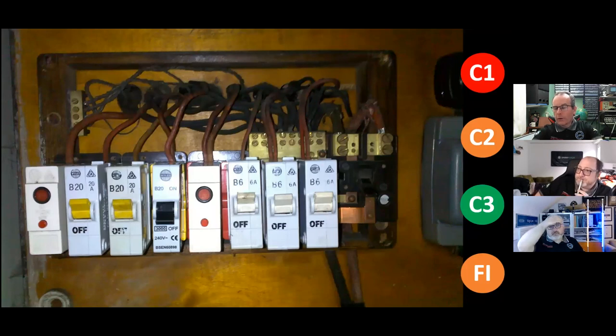And quite honestly, if I hadn't found that before, then I'd be telling the customer there's not going to be a whole lot of point in inspecting the rest of this installation, because if you start taking light switches off and you've got that kind of wiring behind, just taking the switch off is going to cause that insulation to fall off and degrade and fall to bits. So this is definitely one where continuing with an inspection is probably not worth it, because you're going to cause more problems just by taking a socket off and having a look behind.